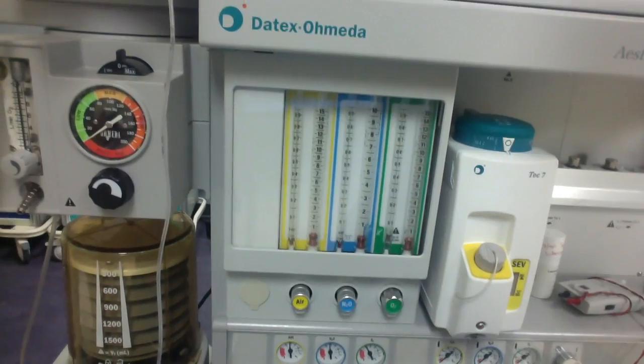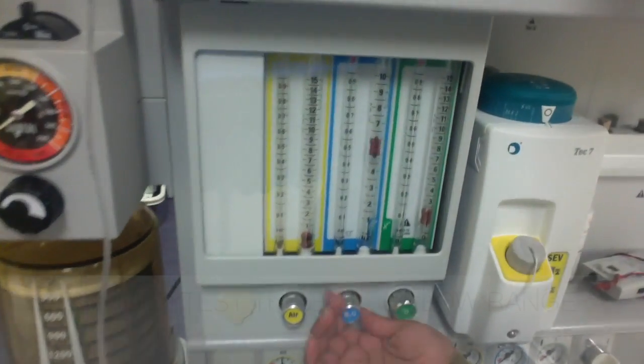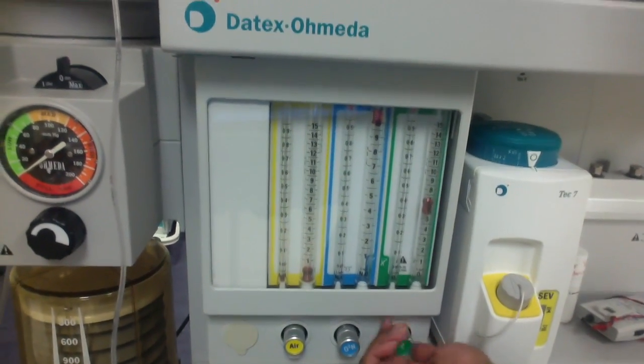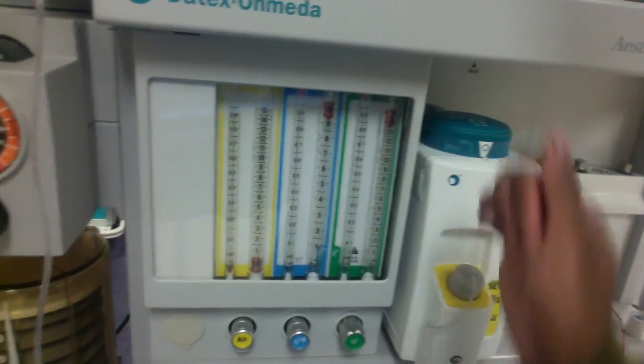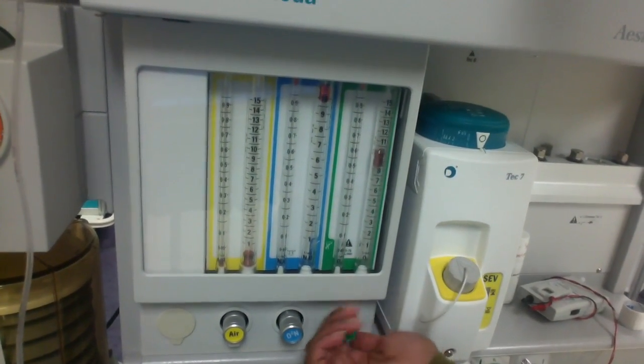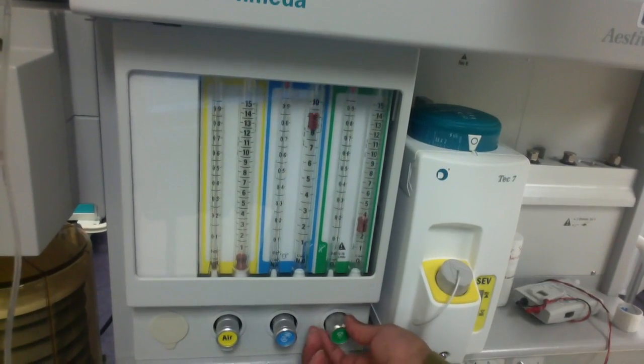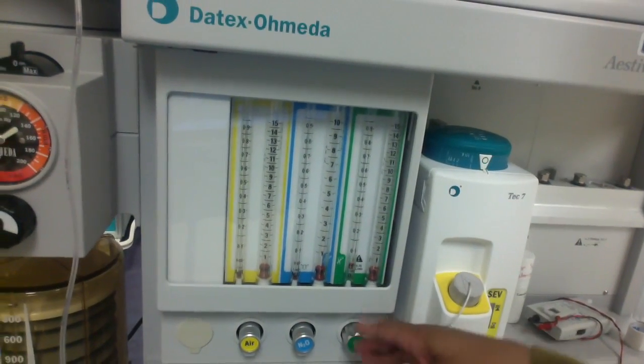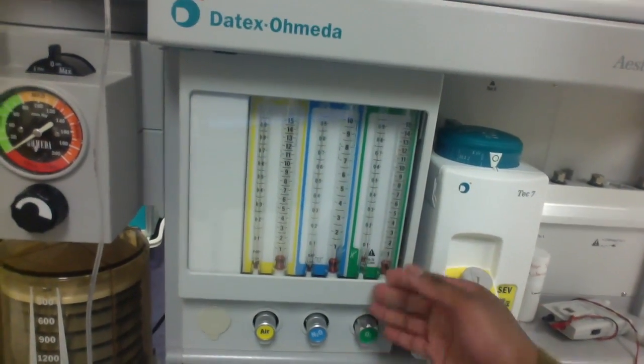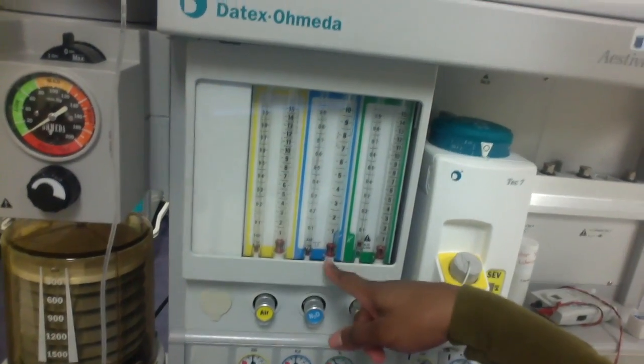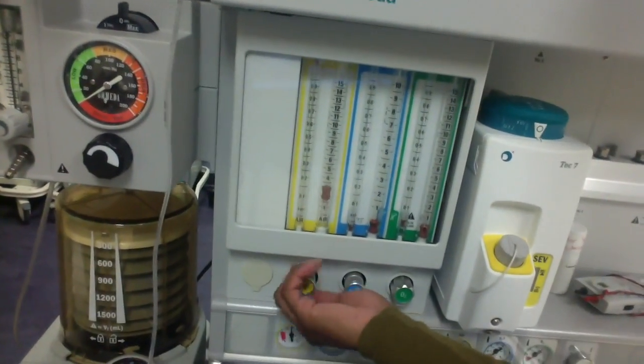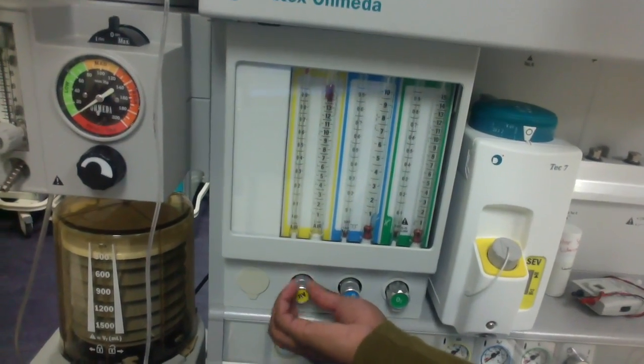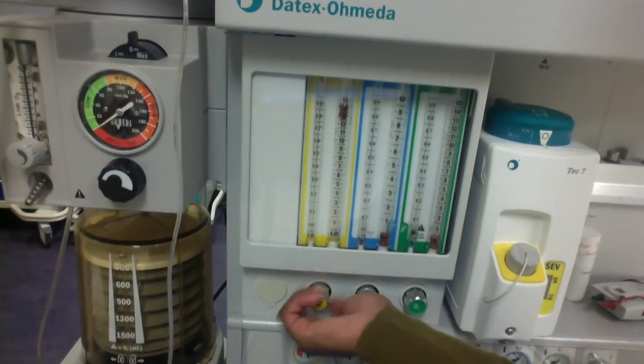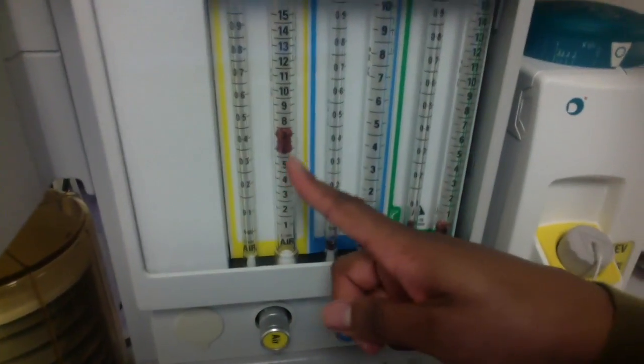They have little measurements that tell you how many liters per minute you are giving your patient. So first I would turn on my nitrous, and I would go the full flow range, and then I would do the same thing with the oxygen, and you'll hear a loud sound, and then I would come back down with my oxygen. So what will happen when I get to 4 liters is that the nitrous will fall as well. And that is a safety mechanism to make sure that I don't give a hypoxic or a low O2 mixture. So if this is off, I don't want to be giving nitrous because then you're not giving oxygen. So I do the same thing with the air, and go all the way up to full flow range and then go back down. And while I'm looking at these, I want to make sure that the bobbin is spinning and that there are no cracks or condensation within these Thorpe tubes.